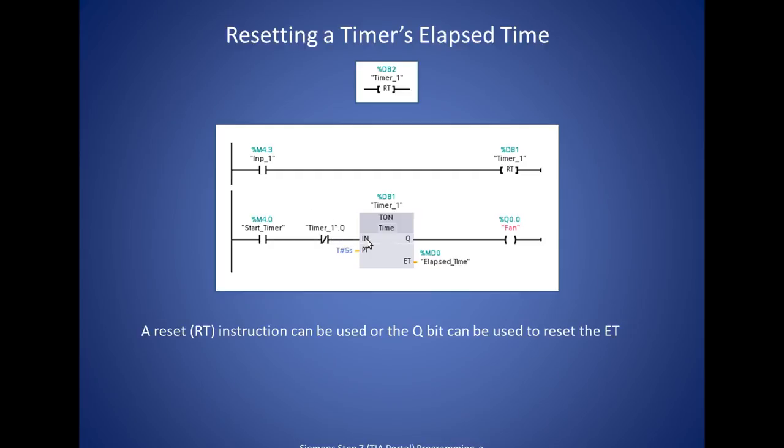And so that would go ahead and reset the elapsed time on this timer. And so the effect of this is to just pulse the output. So this is one way of toggling or setting a memory bit once every so often. In this case, once every 5 seconds, we're going to set a bit to 1 for one scan.